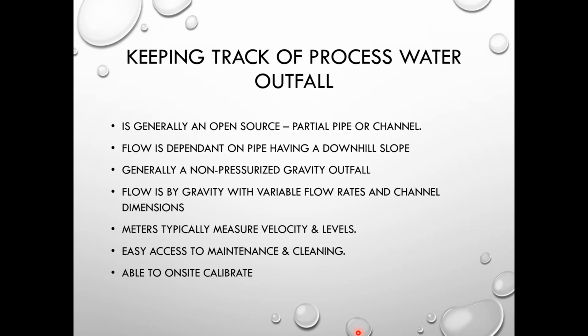Generally, we're talking about a non-pressurized gravity outfall, and we have variable flow rates, variable levels, and variable velocities. So the area continuously changes depending on how much liquid depth you have in your pipe. Meters now don't have to measure just velocity, but they also have to measure the level inside, right? And generally, you want to have a way of calibrating the instrument on site.